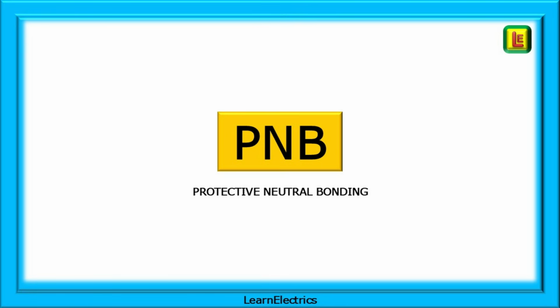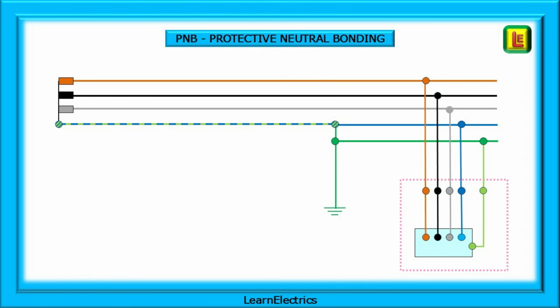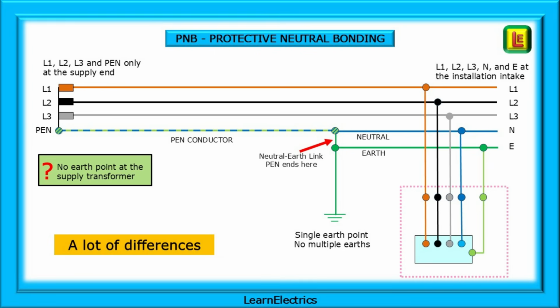Now we can compare PME to PNB, protective neutral bonding. And this is it. This is PNB, as per page 61 of the regulations book, and hopefully it is easier to follow in colour. Let's examine the drawing. On the left we have the supply transformer with the three phases L1, L2 and L3, along with the combined PEN conductor. But no earth point at the supply transformer. That is the first of many differences.